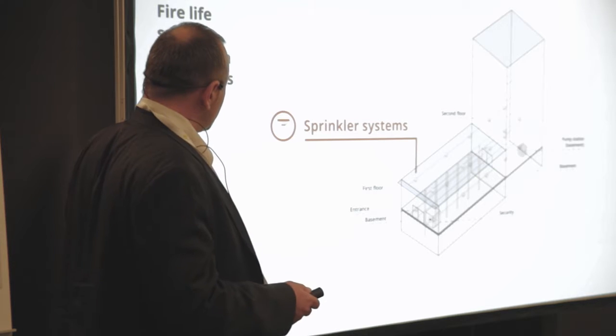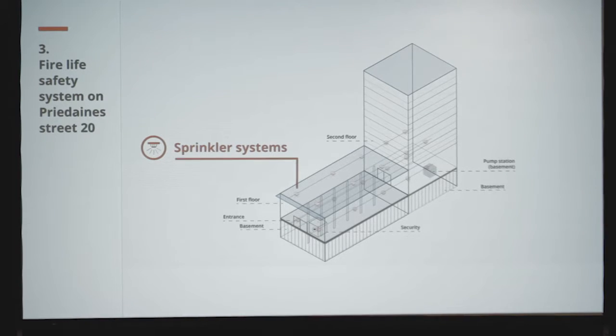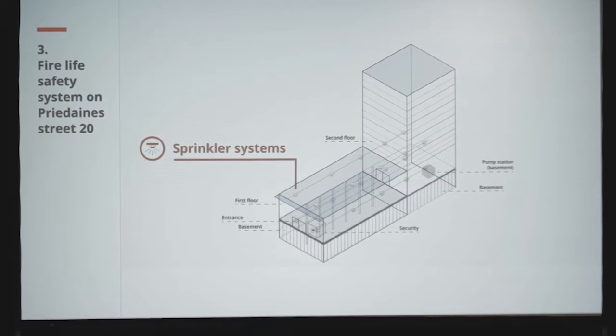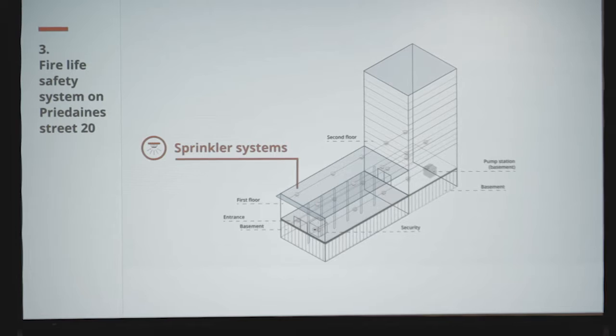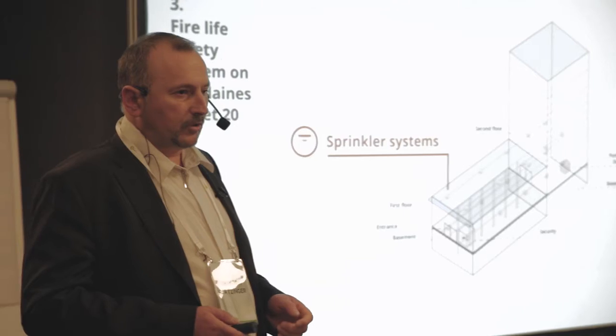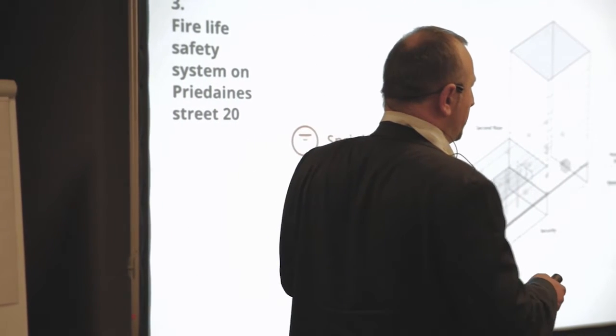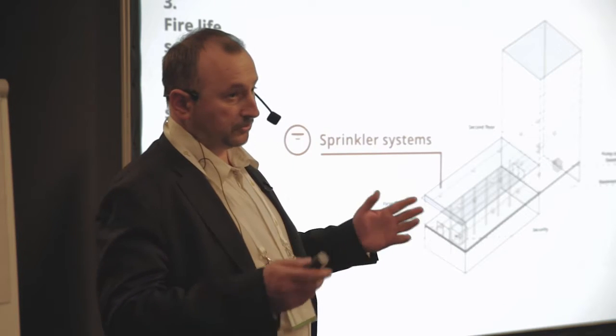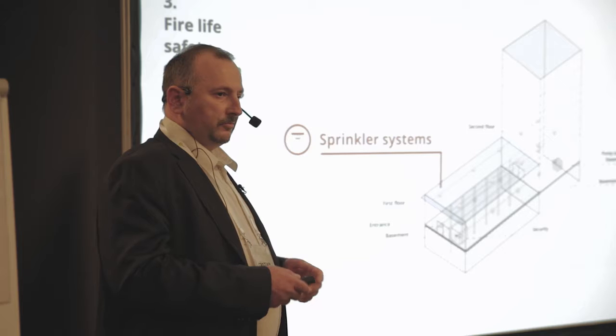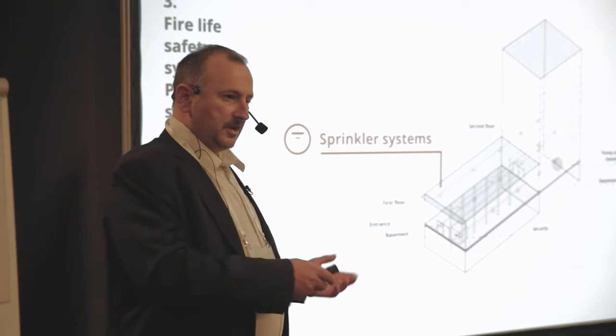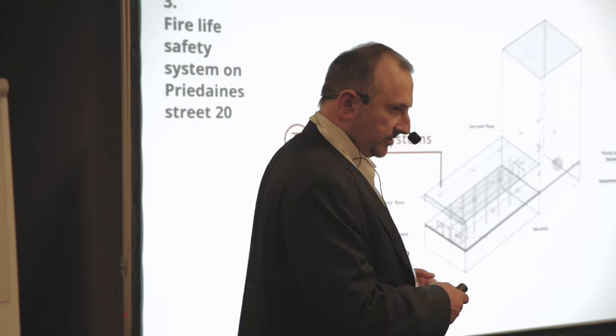Sprinklers were installed too, as well in the underground, as well on the first floor. We've got here two types of sprinklers. One is a wet system, meaning water is inside the pipe. Another one is the dry one. It's concerning the sprinklers in the underground. Why are they dry? Because in the underground parking there could be, normally not, but it could be temperatures which would cause freezing if there would be water inside the pipes.